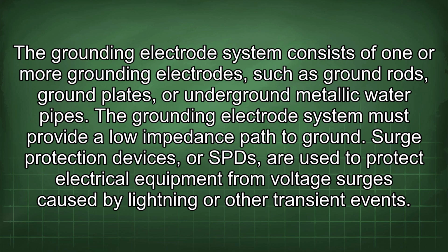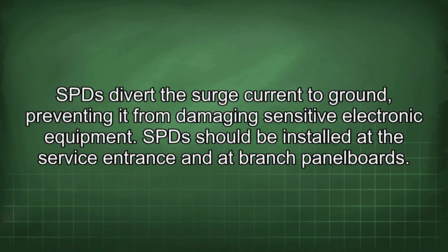Surge protection devices, or SPDs, are used to protect electrical equipment from voltage surges caused by lightning or other transient events. SPDs divert the surge current to ground, preventing it from damaging sensitive electronic equipment. SPDs should be installed at the service entrance and at branch panel boards.